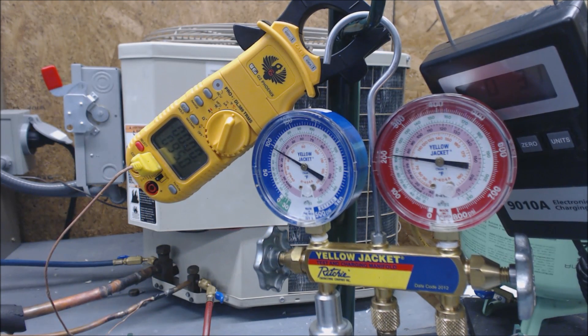I hear no bad noises from the compressor. Once again I have my liquid vaporizer here and that is protecting the system. We want to make sure that we don't have any liquid slugging of the compressor.